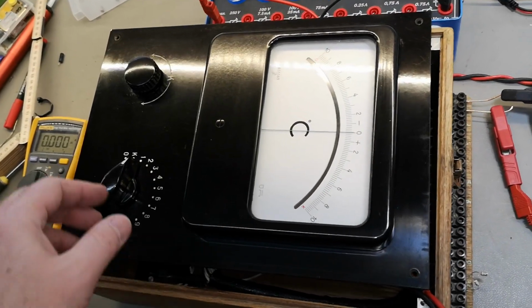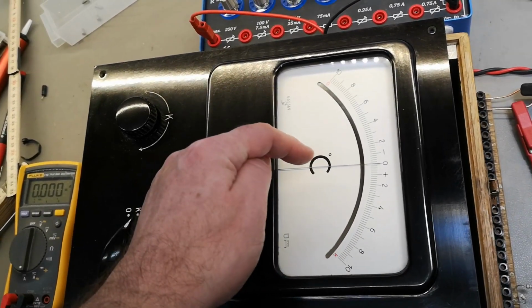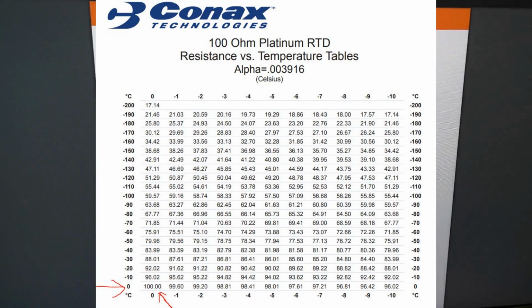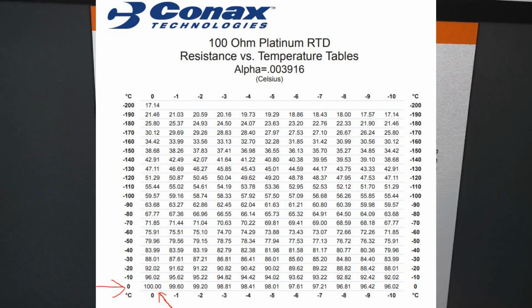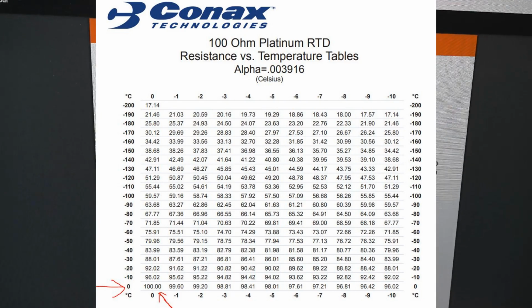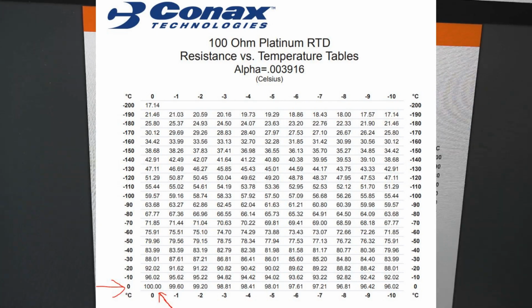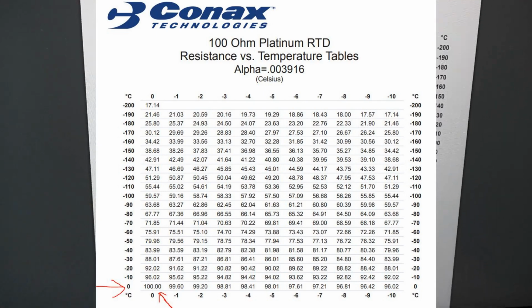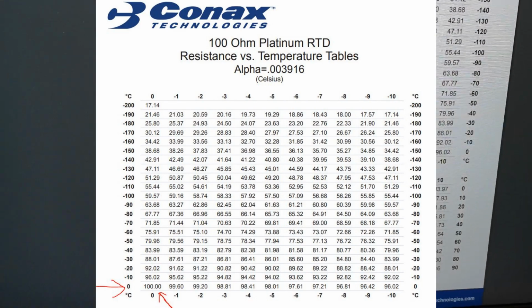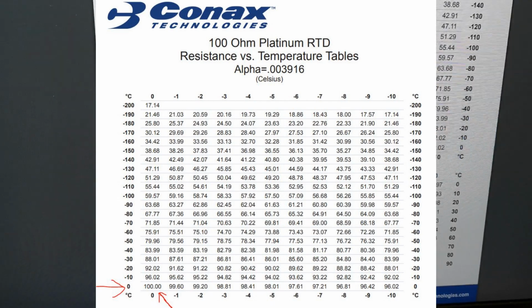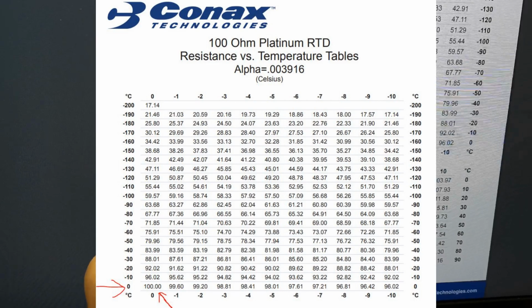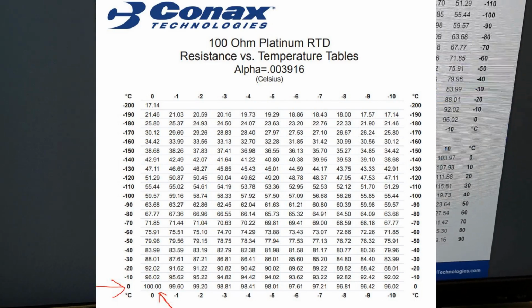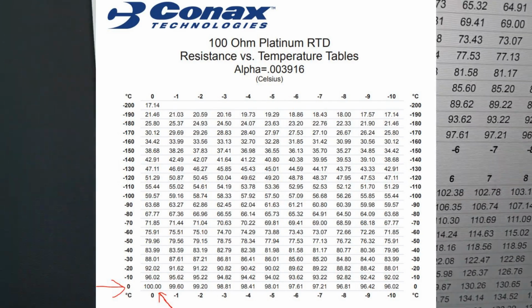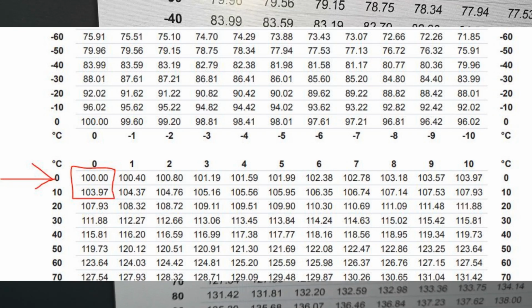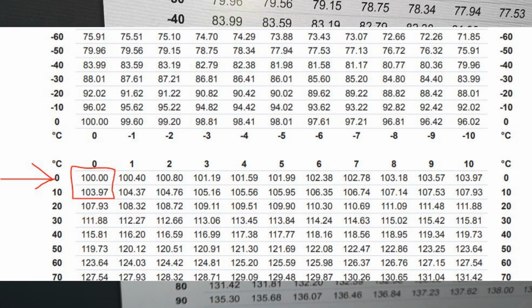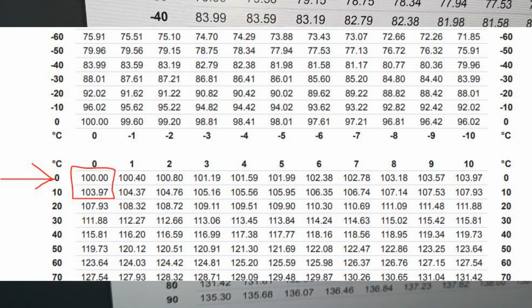Well, maybe we should figure out what kind of sensor that is. That is a little bit interesting to make it read Celsius. That was almost too easy, of course it's a 100 ohm platinum RTD temperature sensor. So look at this, what I found here, a resistance versus temperature table. So here's how it works: at 0 Celsius, the resistance is 100 ohms. So if the temperature is minus 10 or plus 10, it's about 4 ohms difference. So all we have to do is put in a 100 ohm RTD, and then we'll have a temperature meter here that works. How cool is that?